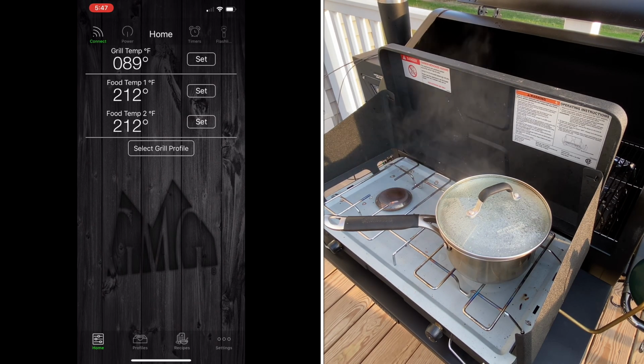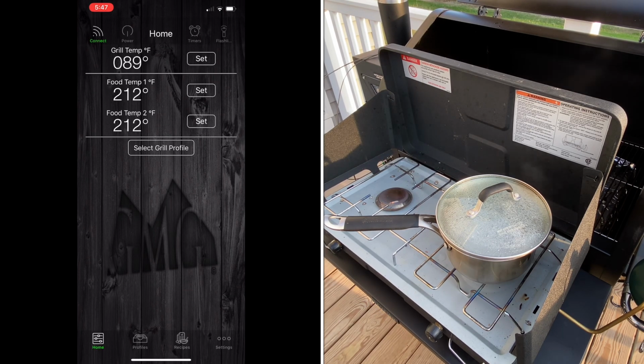Again, my probes seem to be high on both ends, the low end and the high temperature. If your probe's low, you will be putting in +5 or +6 to change the calibration to get your levels to your calibrated known sources.